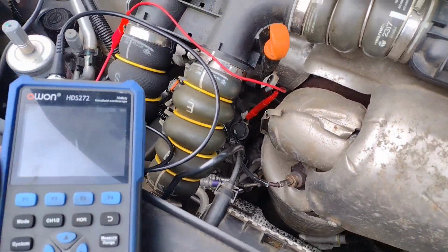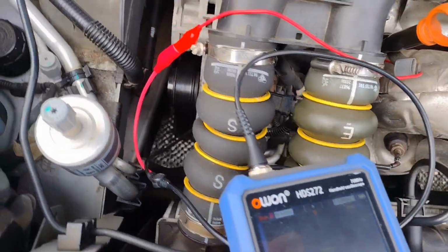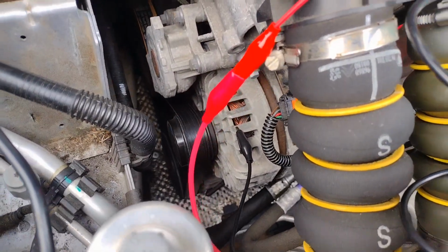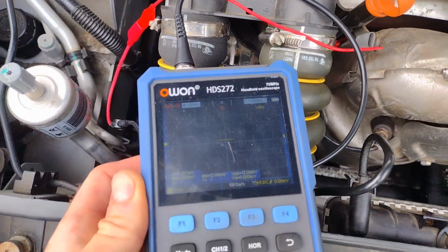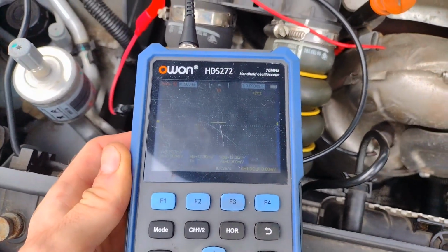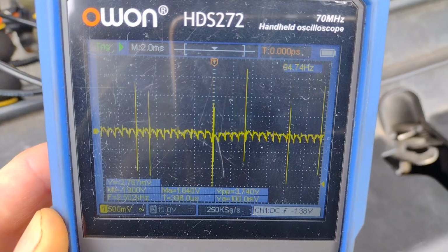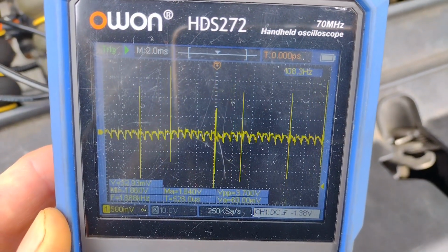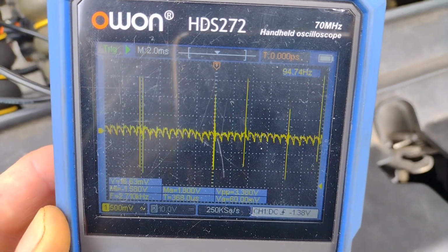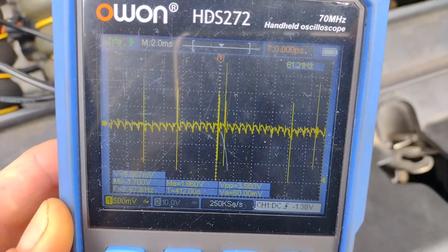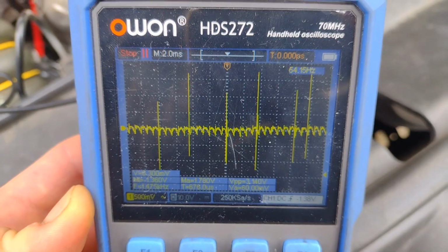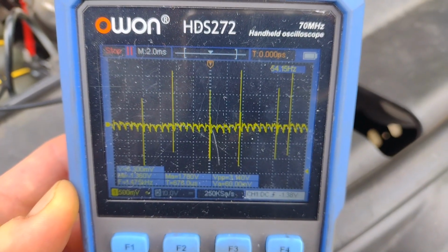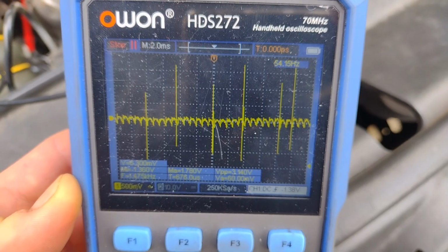The last thing you can do is a ripple test. I've got the oscilloscope hooked up to the positive of the alternator and the negative of the alternator casing, which gives the best signal. This picks up the AC, or rectified AC output, from the alternator. You're just looking for any gaps or big dips there, which would indicate the diodes of the alternator aren't working correctly.